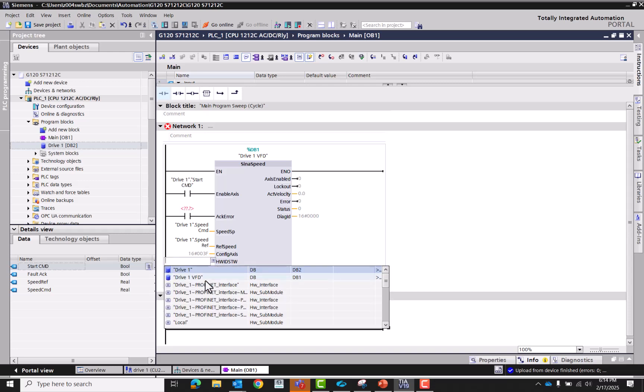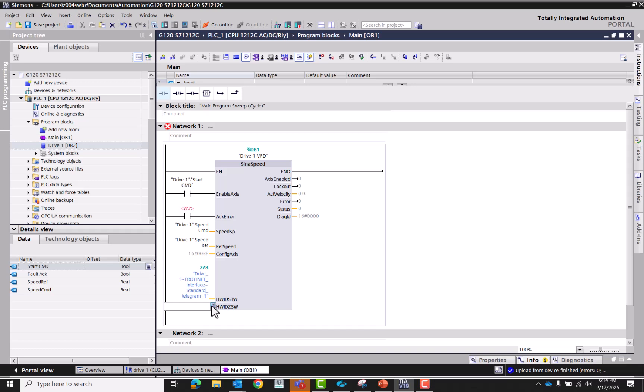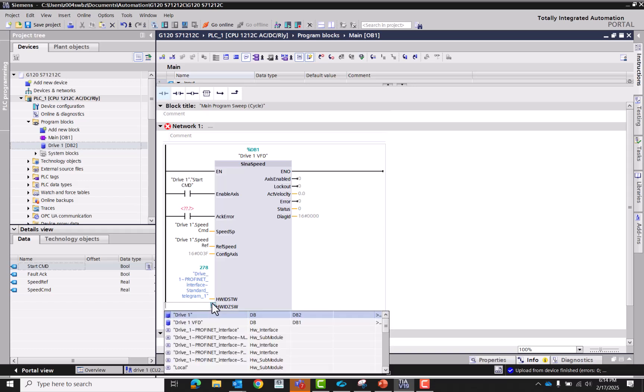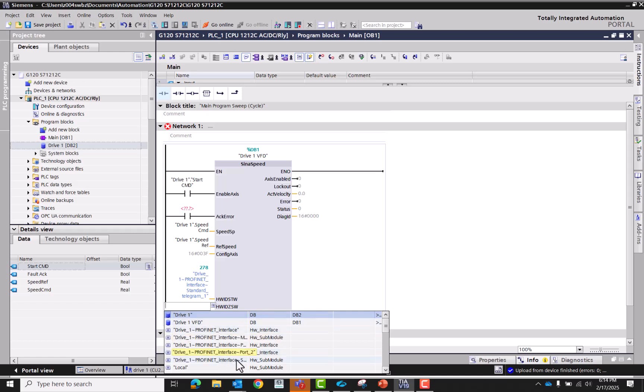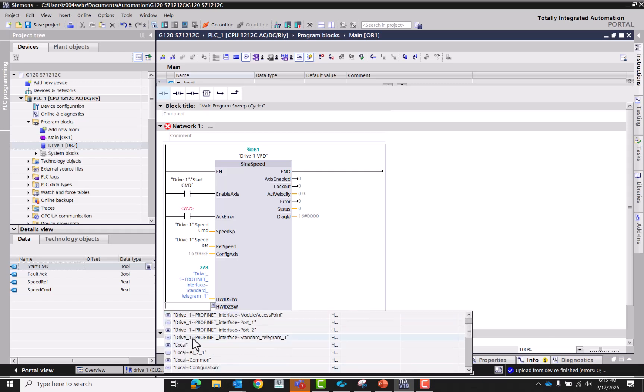Sometimes a little tricky. There we go. Now I'll select the reference speed here. Now these two here is going to be, that drive. You're going to make sure that when you highlight the one you want, says telegram 1. So drive one Profinet interface standard telegram one. And then same thing for the control word. So the first one is status word, second one is the control word.